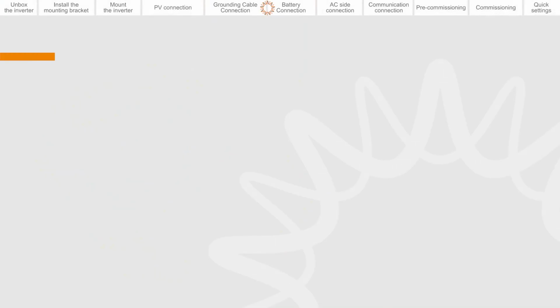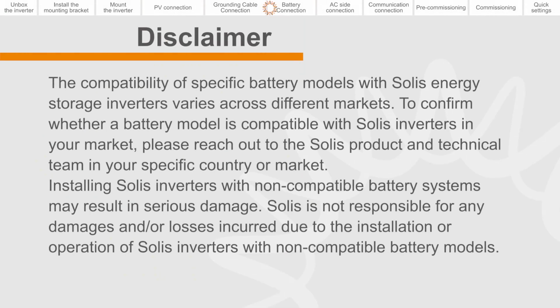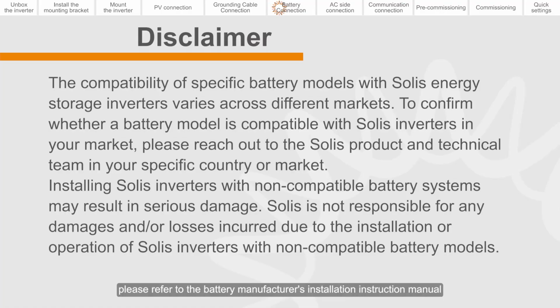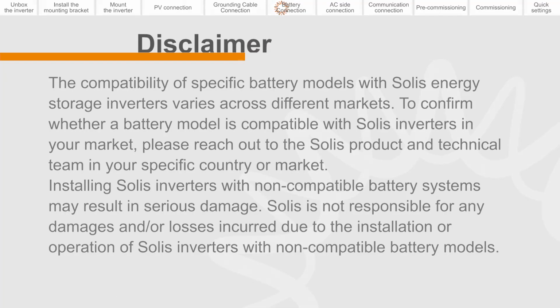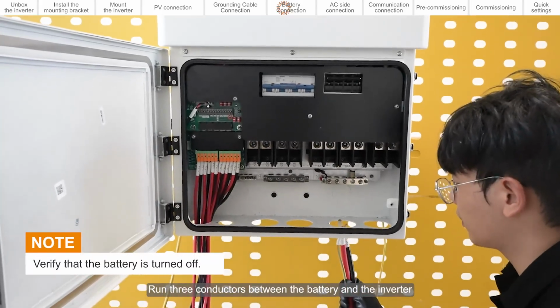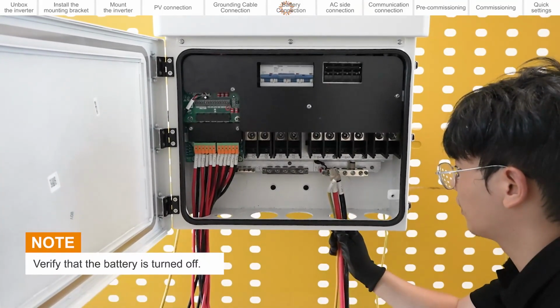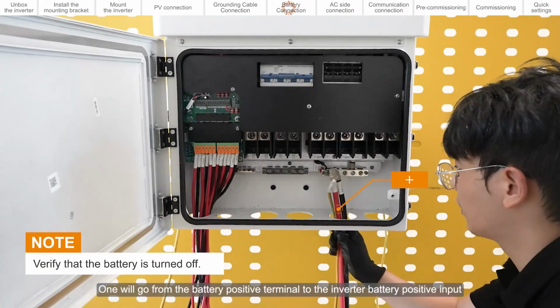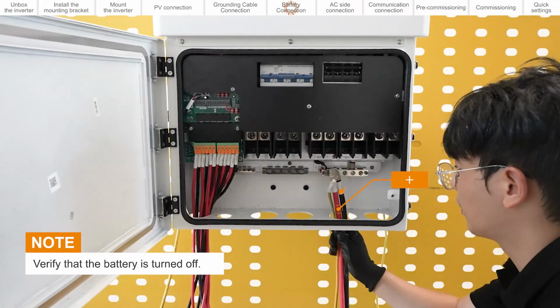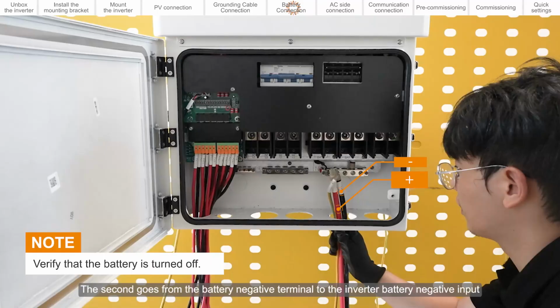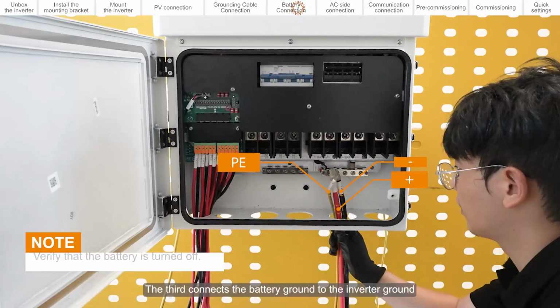Battery connection. Disclaimer. For battery installation, please refer to the battery manufacturer's installation instruction manual. Run 3 conductors between the battery and the inverter. One will go from the battery positive terminal to the inverter battery positive input. The second goes from the battery negative terminal to the inverter battery negative input. The third connects the battery ground to the inverter ground.